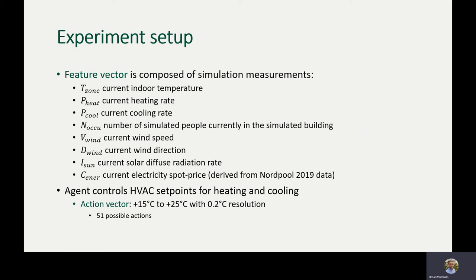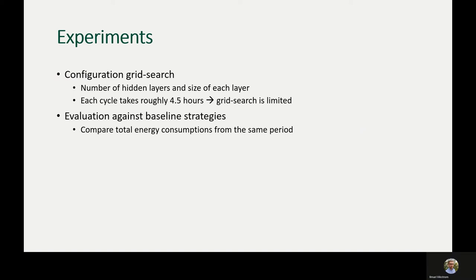The action vector consists of temperature set points for heating and cooling. In this work the agent does not control the power output of the HVAC machinery directly, but rather controls the temperature set points. The temperature range is from plus 15°C to plus 25°C with a 0.2°C resolution, meaning there are 51 different possible actions for each time step.